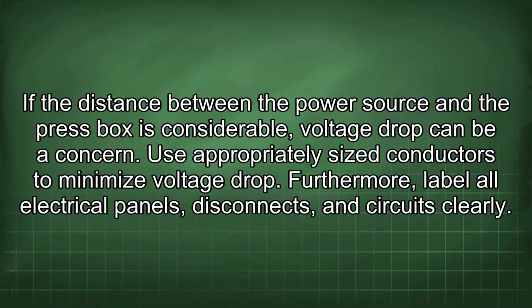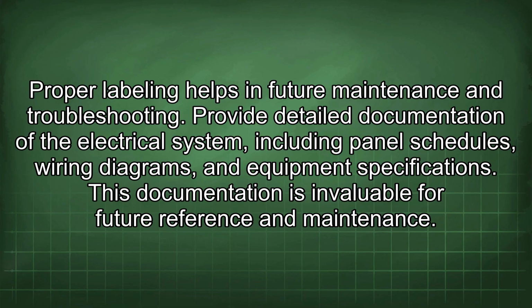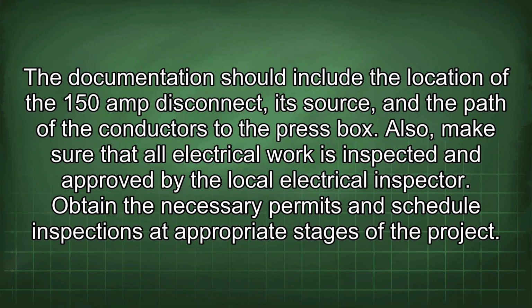Furthermore, label all electrical panels, disconnects, and circuits clearly. Proper labeling helps in future maintenance and troubleshooting. Provide detailed documentation of the electrical system, including panel schedules, wiring diagrams, and equipment specifications. This documentation is invaluable for future reference and maintenance. The documentation should include the location of the 150 amp disconnect, its source, and the path of the conductors to the press box. Also, make sure that all electrical work is inspected and approved by the local electrical inspector. Obtain the necessary permits and schedule inspections at appropriate stages of the project.